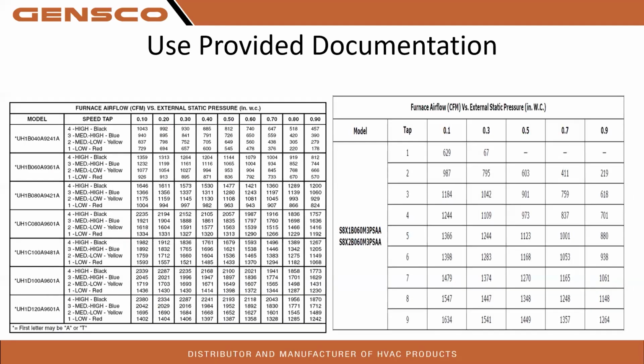And of course, use provided documentation, right? So on these UH models, they're speed taps, PSC motors, they're going to give us a lot of data, right? So if we're using a B60 high, we're going to use black. We have a 0.5 static. We know we should be able to make 1144 CFM at 0.5. Right, so in reference to the S8X, so this is a newer furnace, constant torque, short. At a 0.5 static on tap 5, we're moving 1123. So let's say we're running tap 5 for heat, and we have a 0.7 static. We know we're moving 1001 CFM, right? So we do the math as much as we can for you guys.